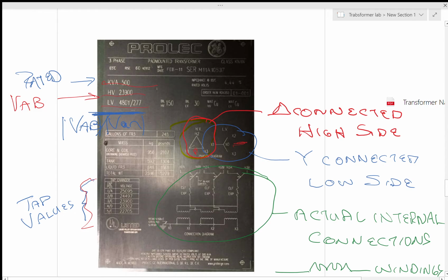And so this is the rated values. Once again, this is our rated, rated. And this is three-phase power, because it's a three-phase transformer. It says so right here, three-phase transformer. GE ProLec tells you how much it weighs, how much oil is in there, all that good stuff. Tells you the serial number, just in case you have to parallel a set of these transformers. You can send GE that serial number. They'll find out exactly what the impedance of the transformer is, and they'll match it to your new one. Don't have any problems.